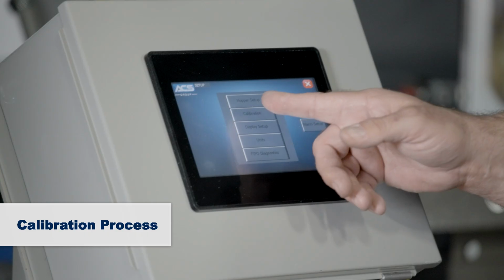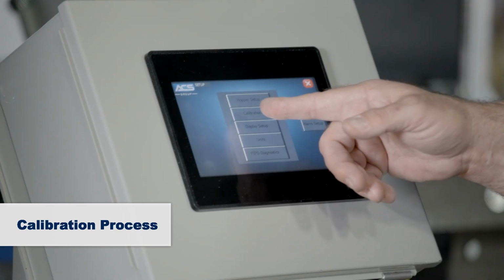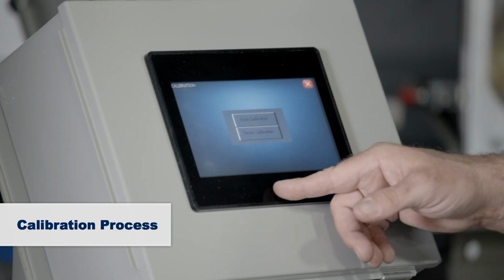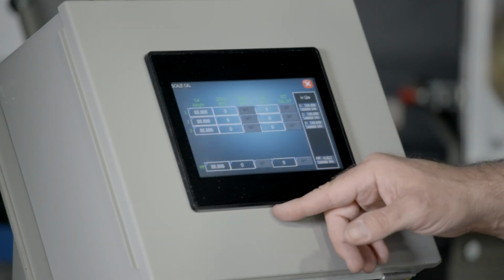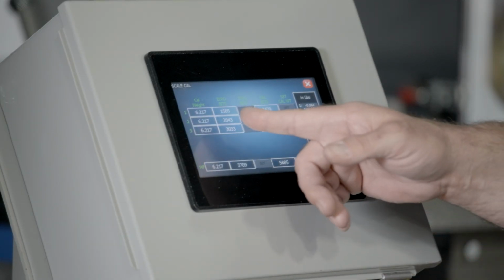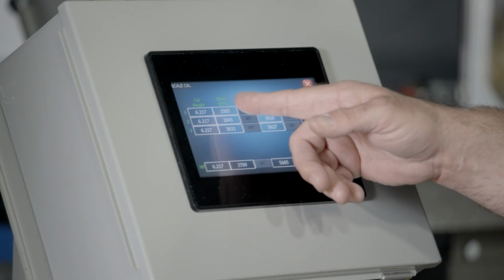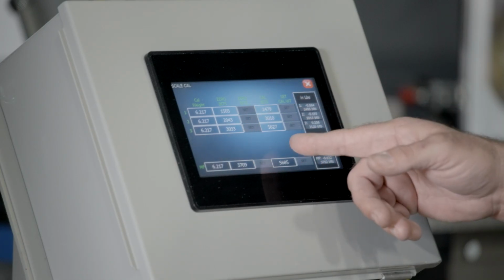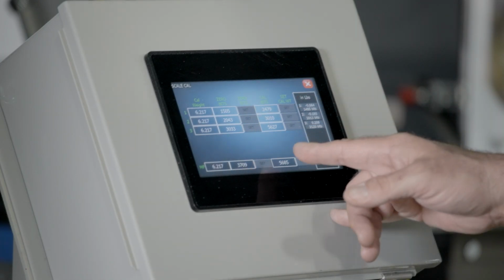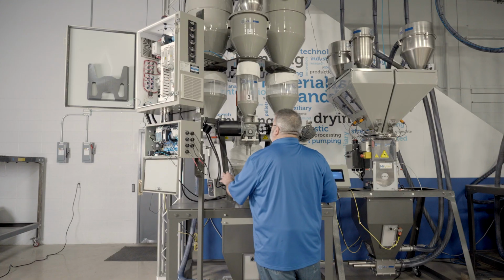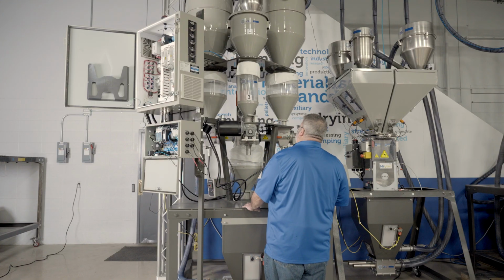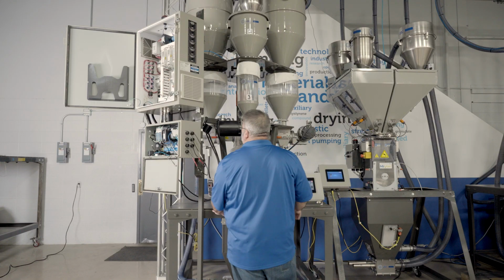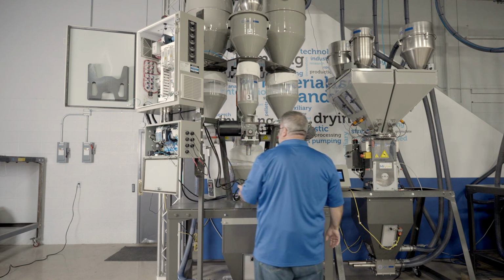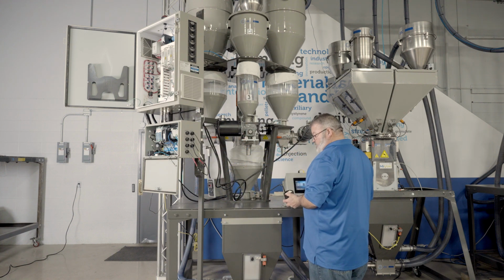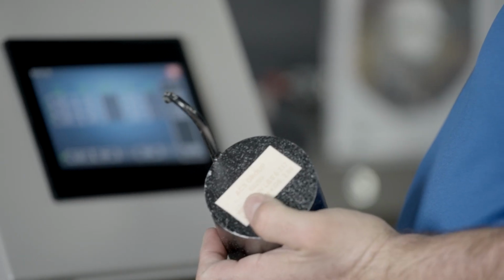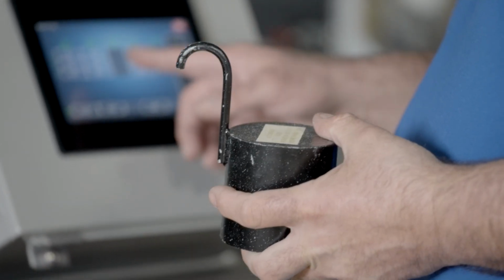Next we'll do calibration. To calibrate, you touch calibration, scale calibration, and it's going to show you your cal weight value, your zero, and your tare. So to calibrate this unit, where did the weight go? I just saw it. There it is. We'll get our known calibration weight stamped on this weight. It gives you what it weighs, so we'll make sure that matches here.